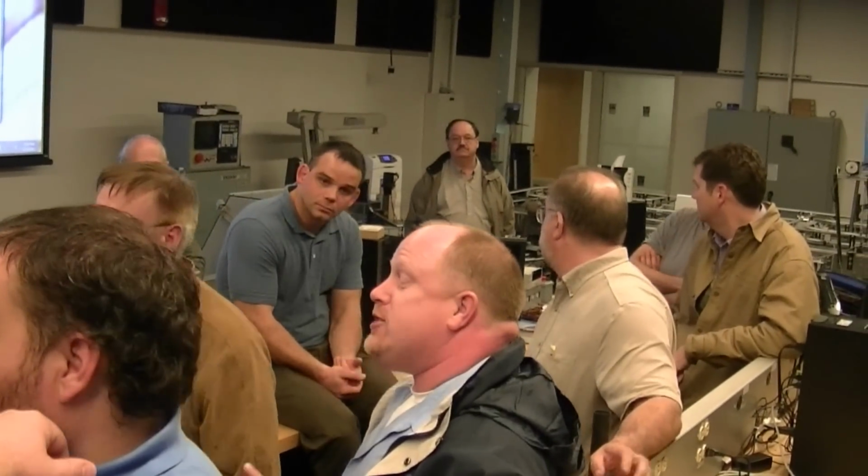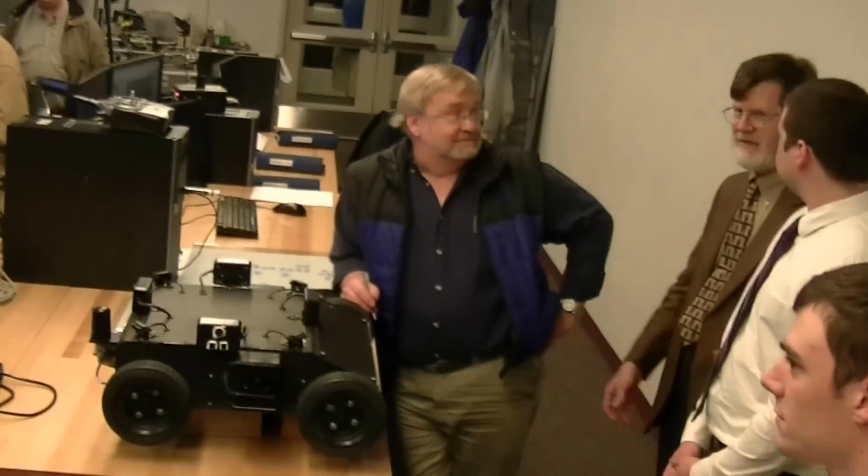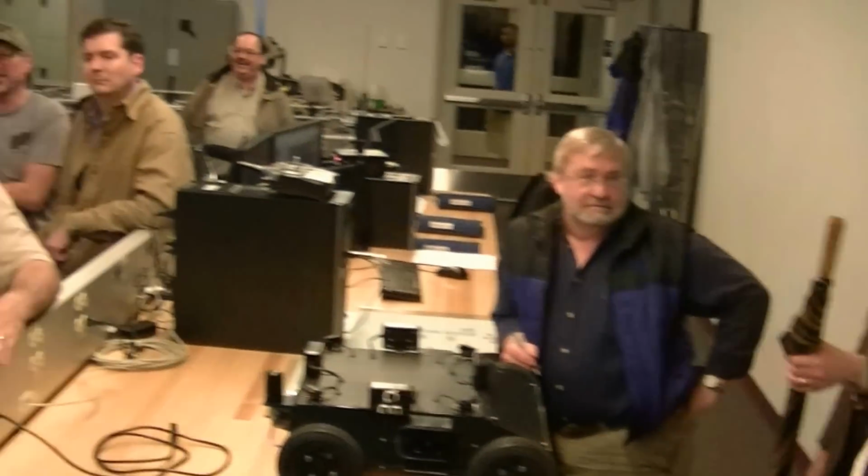Yeah, well, in actuality, the PIDE is actually easier to tune than a ladder PID. Is it really? Yeah, I don't know why, but it is. It also offers auto tuning, but the auto tuning really sucks. Rockwell screwed that one up. Say that again.